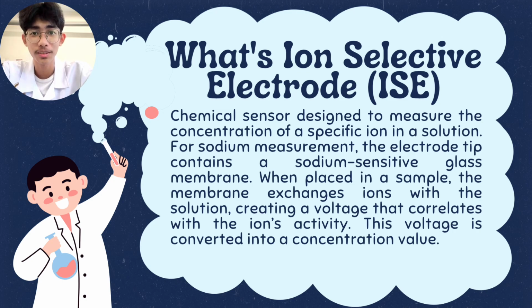So what is an ion selective electrode? ISE is a chemical sensor designed to measure the concentration of a specific ion in a solution. For sodium measurement, the electrode tip contains a sodium-sensitive glass membrane. When placed in the sample, the membrane exchanges ions with the solution, creating a voltage that correlates with the ion activity. This voltage is converted into a concentration value.